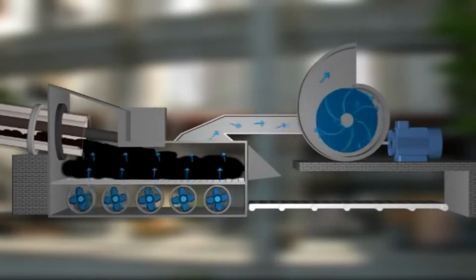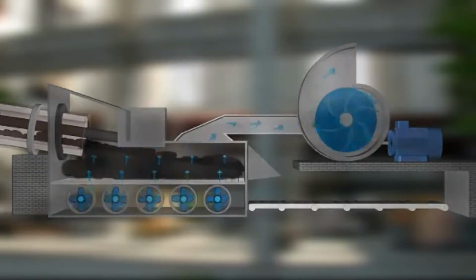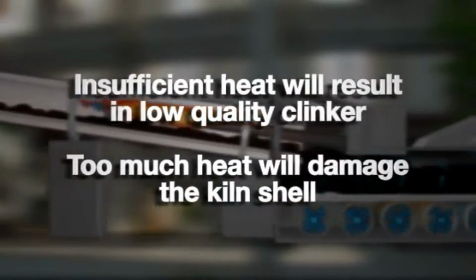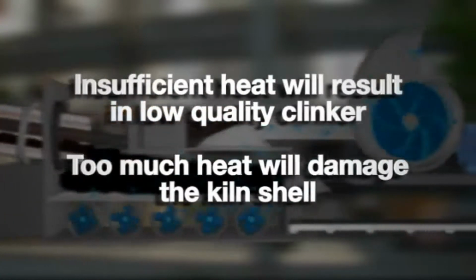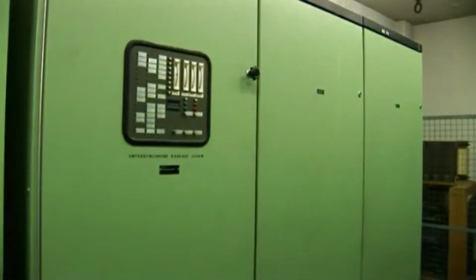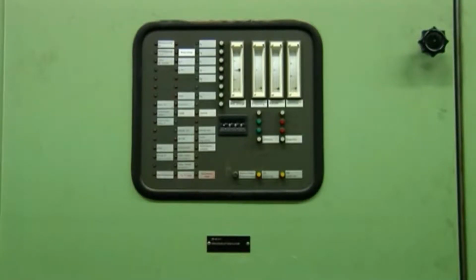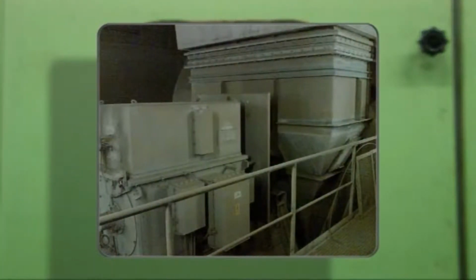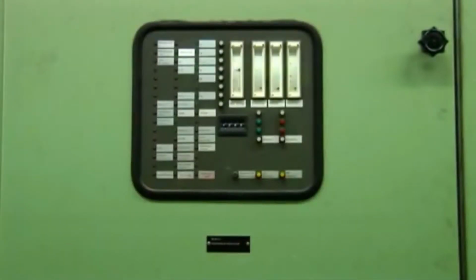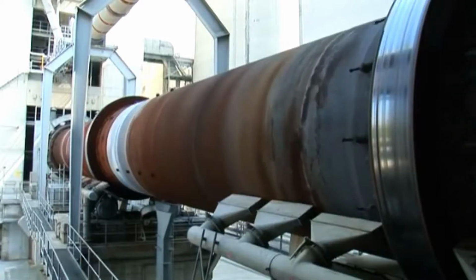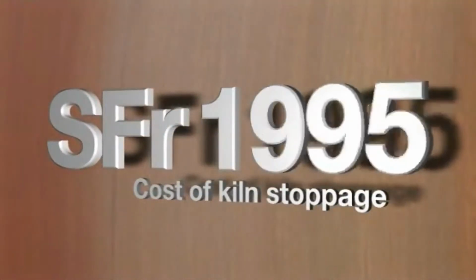Accurate energy input is critical to the quality of cement. Insufficient heat will result in poorly burned, low-quality clinker, whereas excess heat might damage the kiln shell. Previously, Jura Cement used this 630 kilowatt cascade drive, controlling a slip ring induction motor. But after 25 years, spare parts were becoming scarce, and the maintenance costs were escalating, partly because of the need to replace the carbon brushes on the slip ring induction motor every 3 months. And with each kiln stoppage costing several thousand Swiss francs, maximizing uptime of the process is paramount.